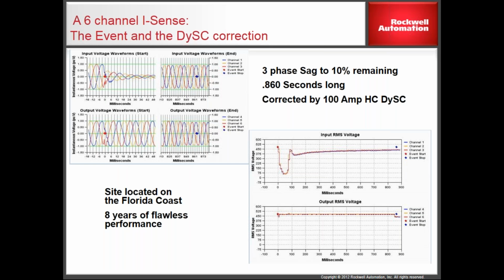At 9 cents a kilowatt hour, here's a rule of thumb: 100 amps of three-phase UPS protection is going to cost you $10,000 a year to trickle charge the batteries. You'll spend $600 in that same year on a DySC. Even that little UPS you might be using in your control cabinet today, on average, costs $350 a year trickle charging the batteries in that little bin at the bottom of the cabinet, just due to the efficiency.